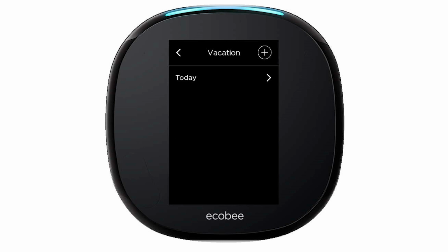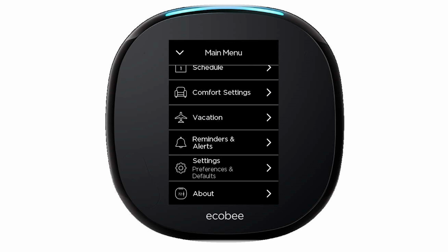It's going to ignore any occupancy. So if there's any motion, any occupancy read out of room sensors, when it's in vacation mode, it's going to completely ignore that. So it's going to act just like a traditional thermostat in that it will just hold that set point. So if you have someone coming in the house to check your mail, someone that's coming to walk the dog or something, the system will not kick on based on an occupancy read. So this is a nice feature.